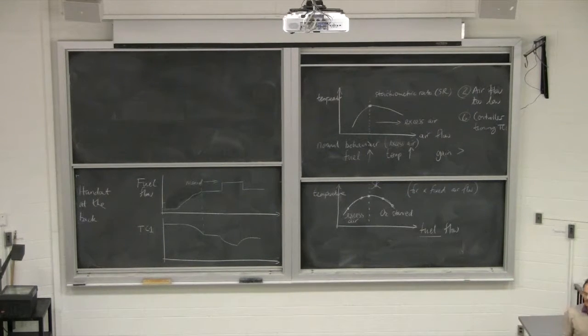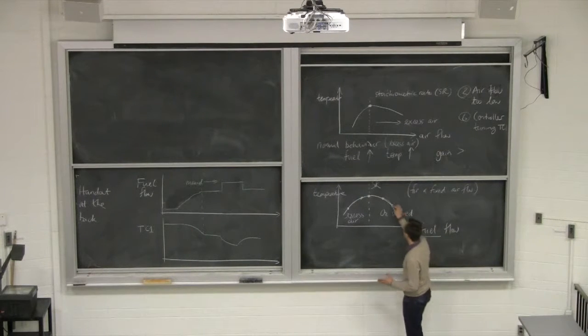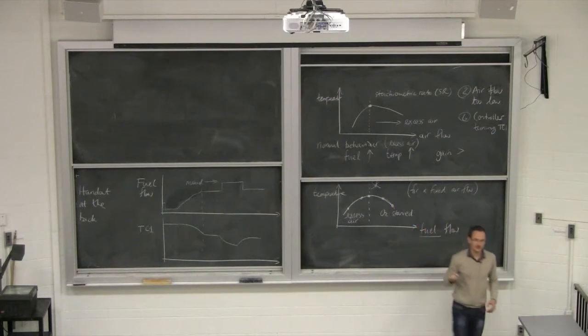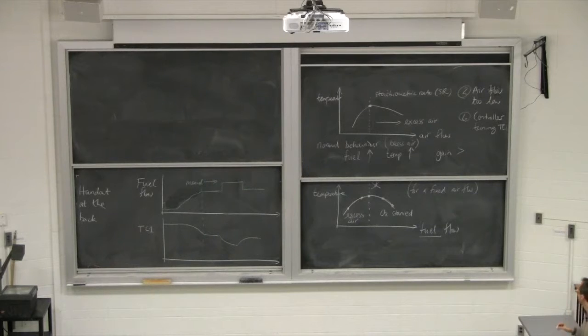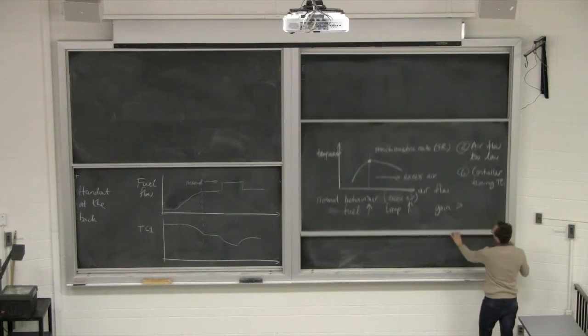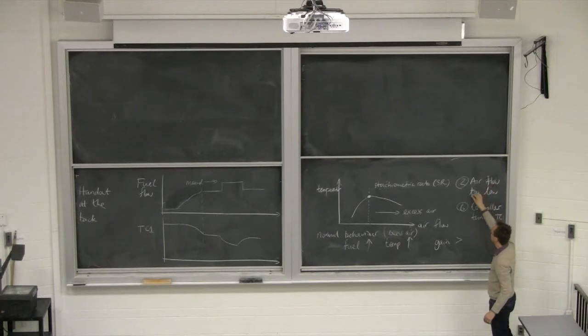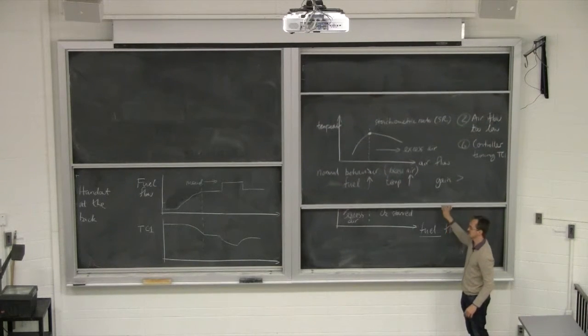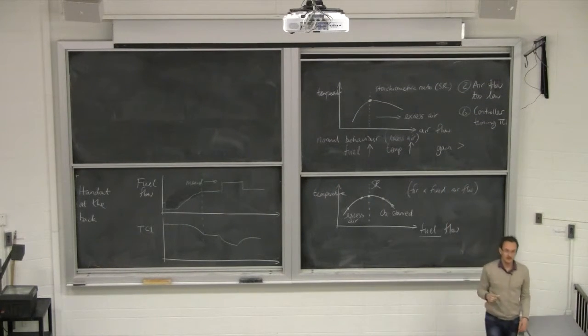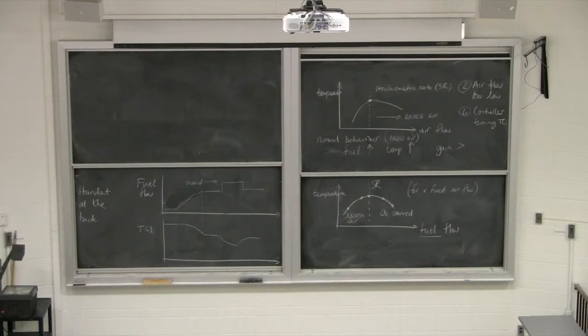So let's take a look now. If you were faced with this problem at this particular point, right, so you may have figured this out, that there's this problem with a control loop. Or certainly you've figured out, at the very least, these two are just a restatement of each other. This one is more the outcome as a result of part two. So what can you do to fix this as a short term? If you were an operator or you were working with the operator, what would your instructions be to do next? Increase airflow to the heater. Just to like go back to like how you're operating like before the second step change. Which is to drop back down in feed flow. Drop back down in feed flow. But I want, so suggestion to drop back down in feed flow is suggestion to increase the oxygen.